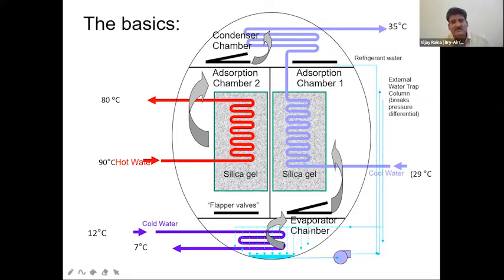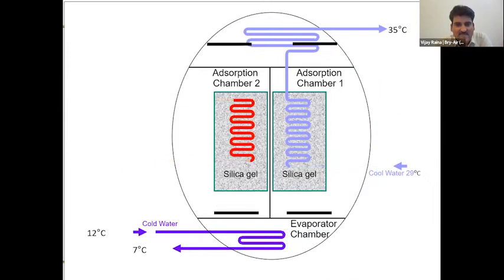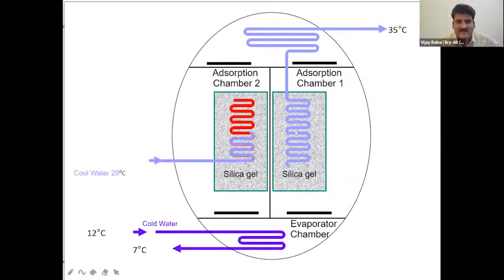This evaporation chamber is simply a shell and tube heat exchanger like in our conventional chillers. The condenser is again simply a heat exchanger as in conventional mechanical chillers. Only the middle portion, adsorption chamber 1 and adsorption chamber 2, is replaced. We have replaced the compressor with silica gel technology. The silica gel works in a cyclic cooling and heating mode, where we use one cooling tower water and another regeneration hot water. So after 5 minutes, there will be a change in the cycle, and a change in the flow of cooling water and hot water, because when the adsorption chamber is adsorbing the water vapor refrigerant, it becomes saturated in 7 minutes or 6 minutes. So we now have to make that adsorption chamber hot and regenerate it, so that it releases whatever it has adsorbed in the first cycle.